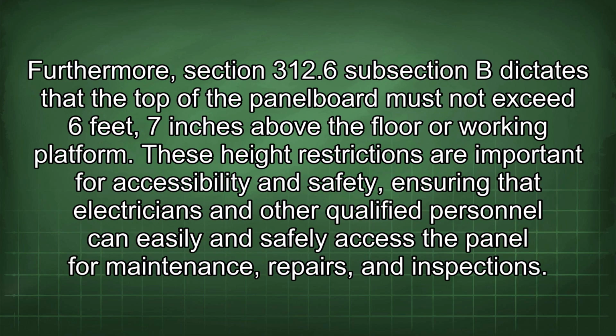Furthermore, Section 312.6 subsection B dictates that the top of the panel board must not exceed 6 feet 7 inches above the floor or working platform. These height restrictions are important for accessibility and safety, ensuring that electricians and other qualified personnel can easily and safely access the panel for maintenance, repairs, and inspections.